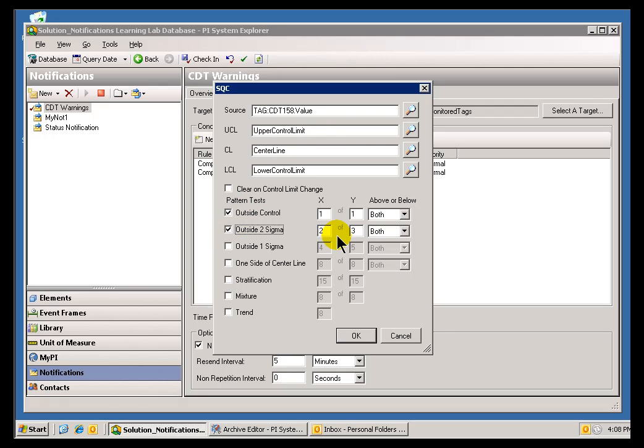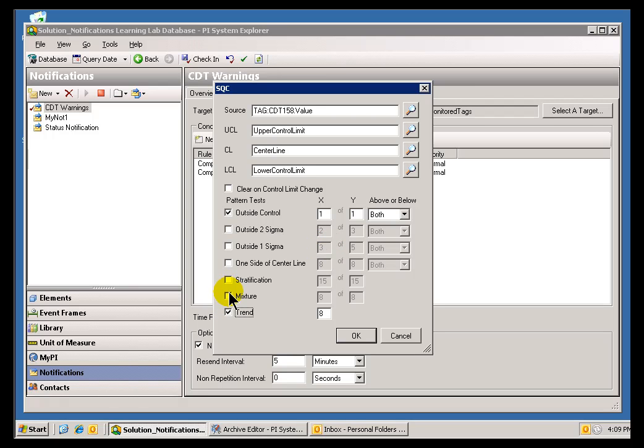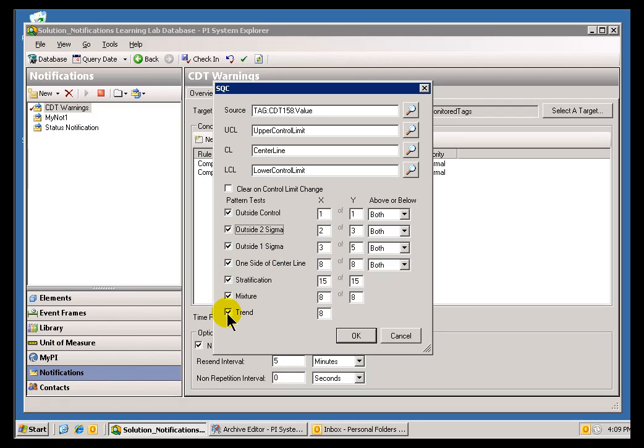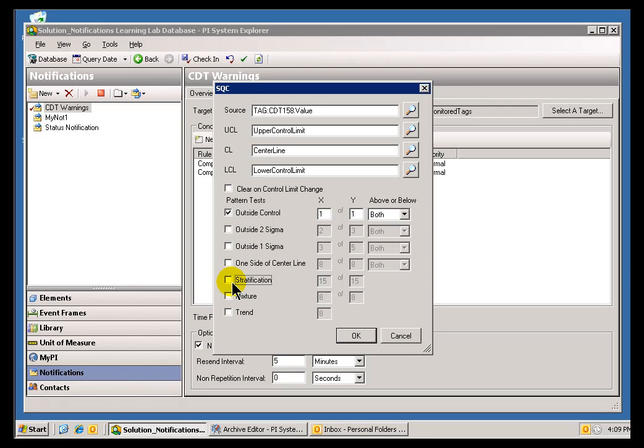You can say if two out of three are outside two standard deviations, or four out of five, or three out of five, it's up to you. Now, we typically suggest people start out slow with any kind of SQC, simply because if you turn on all of these, you're going to just pummel people with all kinds of notifications that are probably fairly difficult and obscure to interpret. So, it's always good to start small. I mean, if you've got a real good group that knows the difference between outside three standard deviations and a Stratification Alarm, then that's something you can choose to do, but we generally recommend you start small.